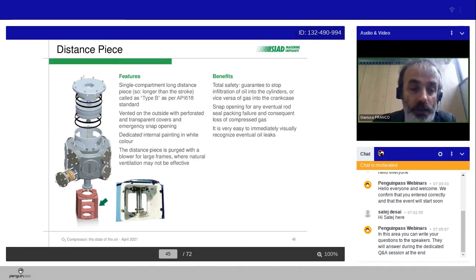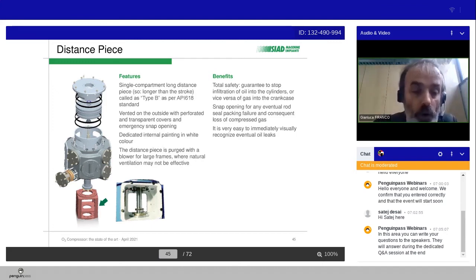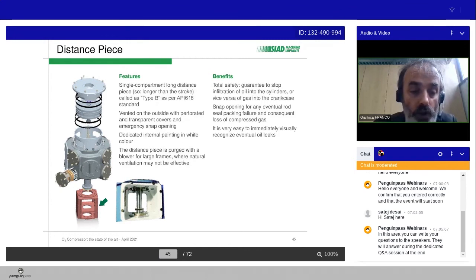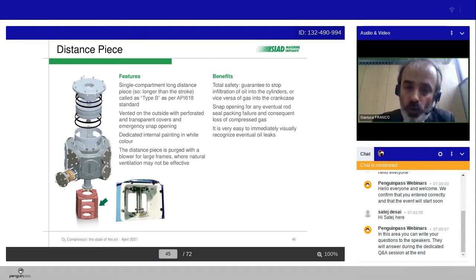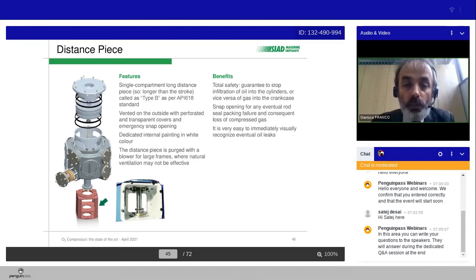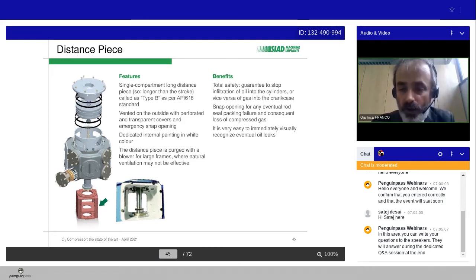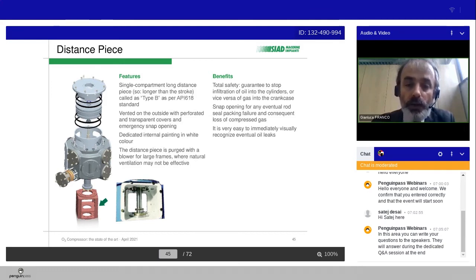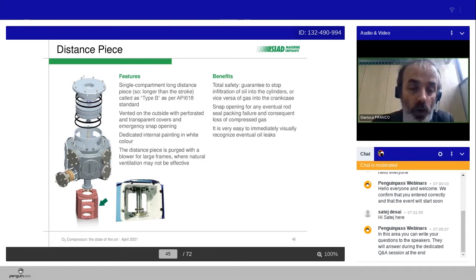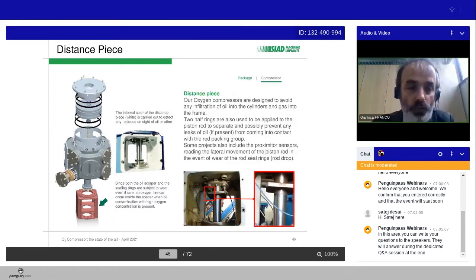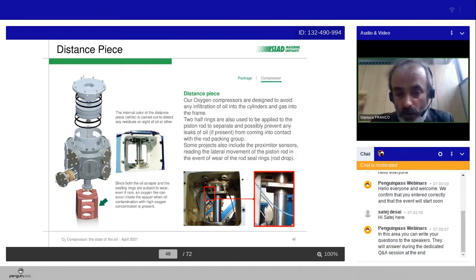The distance piece is purged with a blower for large frames, where natural ventilation may not be effective. Which are the benefits to operate in such a way? Of course, total safety, guarantee to stop infiltration of oil into the cylinders, or vice versa, of gas into the crankcase. Snap opening for any eventual rod seal packing failure and consequent loss of compressed gas. It's very easy to immediately visually recognize eventual oil leaks due to the white color here.